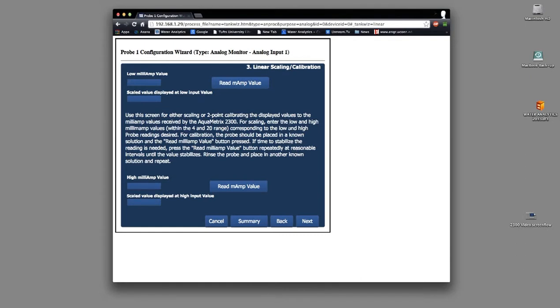With the 2300, you can click on Read Milliamp Value as often as you want, so that you can actually check the actual probe reading. You don't lock in the reading until you go to the next screen. So go ahead and click as often as you want until you're satisfied that the reading has settled down.